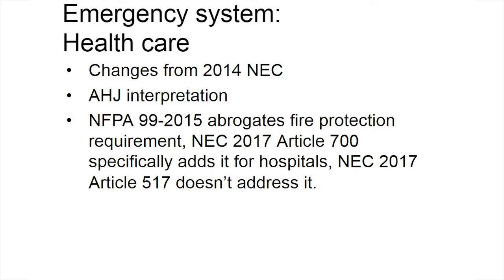And the handbook had warnings that spaces above the ceiling weren't protected unless there were fire sprinklers specifically installed above the ceiling. Later, the handbook dropped that warning and said that circuits installed in a fully sprinkled building were generally adequately protected. But then in 2014, the warning came back and the list of affected occupancies was deleted, so the requirement appeared to apply to almost everything. Then in 2017, the occupancy list came back, and it got bigger to include hospitals and certain educational facilities. The handbook continues to maintain the warning that the above-ceiling spaces aren't protected by sprinklers in the occupied zone.